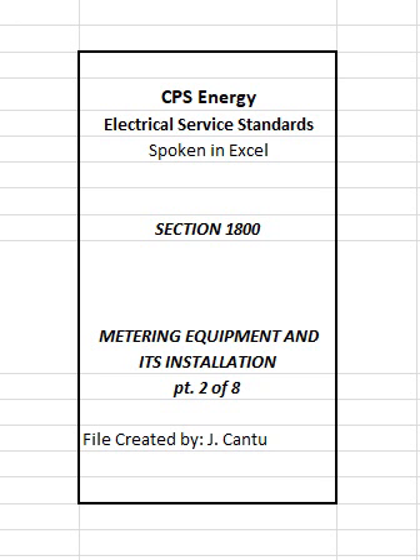B. Instrument transformers, current transformers/voltage transformers. CPS Energy furnishes and installs the necessary current transformers, CTs, and voltage transformers, VTs, that are required for service installations. CPS Energy also furnishes and installs the metering control cables from the instrument transformers to the transformer-rated meter socket. Most CTs are window type, donut type, with the service conductor passing through the CT opening and serving as the primary winding, refer to definition of instrument transformer and Figure 1813. Exception. Customer installs instrument transformers where they are to be installed within customer-furnished metering enclosures, switchgear, or switchboard or in other cases where directed by CPS Energy.